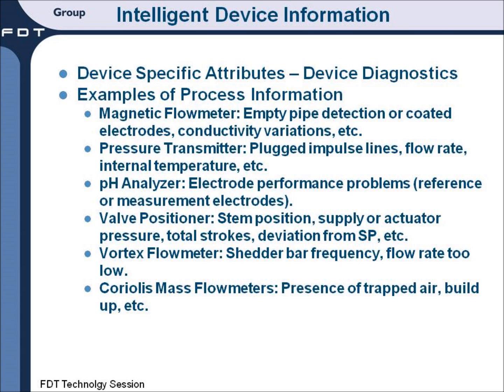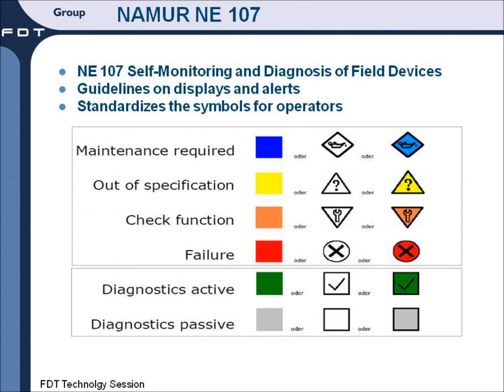The second category of information is device diagnostic information — it's specific to a particular product type. Here's a list of examples of different types of measurement devices you may find in your facility and the kind of information they could give you. In the case of a magnetic flow meter, for example, it may give you an alert or indication that there's empty pipe or that you have coated electrodes. In the case of a pH analyzer, it may give you an indication of a bad reference electrode. Or in the case of a vortex meter, it may indicate that the flow rate is too low to get an actual measurement. In any case, it's all information that can improve your plant reliability and hopefully avoid any kind of unscheduled shutdowns.